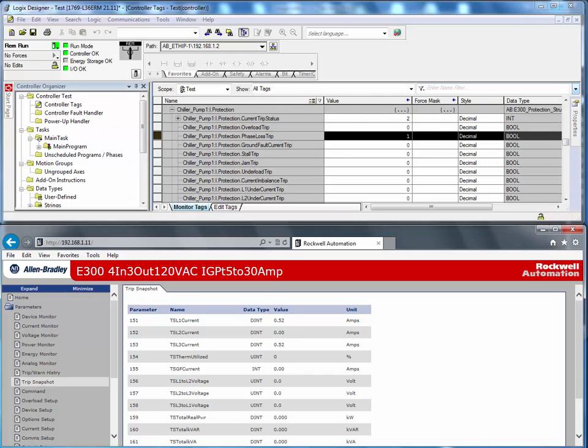Using this information, maintenance staff can interrogate the E300 Electronic Overload Relay remotely, understand the reason for the trip, and identify the reason why the trip occurred. In this example, we can send out a maintenance person to go and replace the fuse on L2 for this particular motor starter.